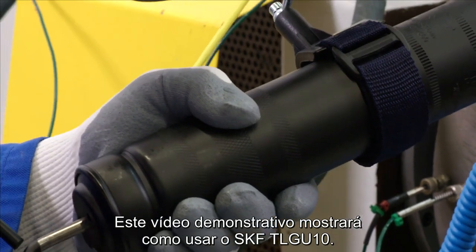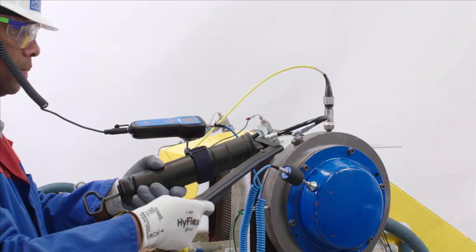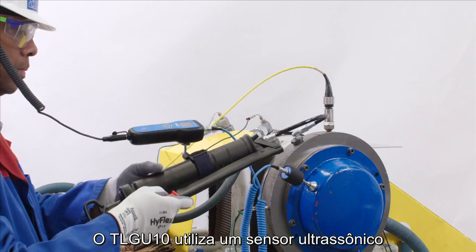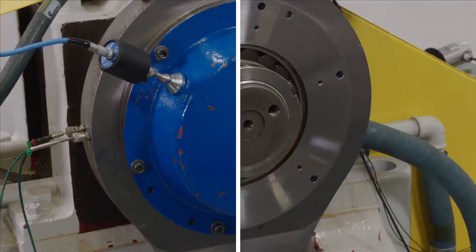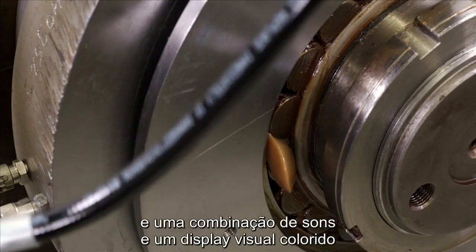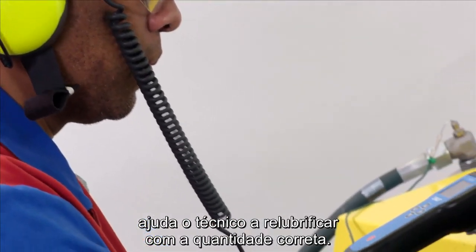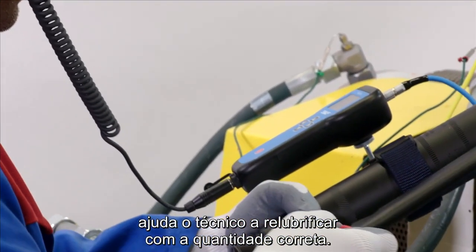This instructional video will show you how to use the SKF TLGU10. The TLGU10 uses an ultrasound sensor to monitor the sound of lubricant filling the bearing, and a combination of sound and a color visual display helps technicians to re-lubricate with the right amount.